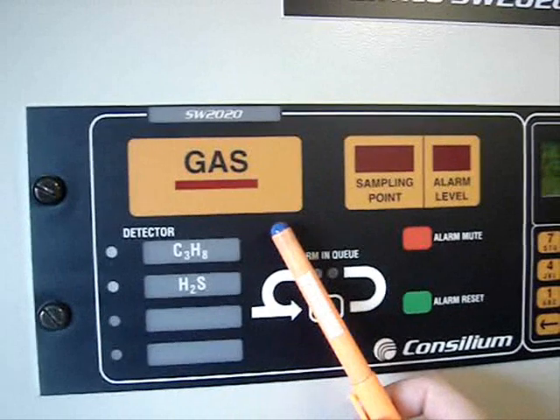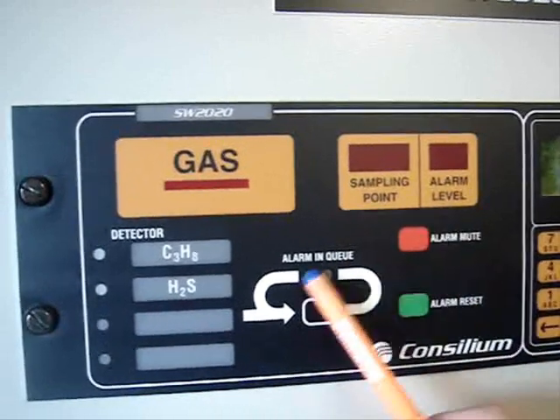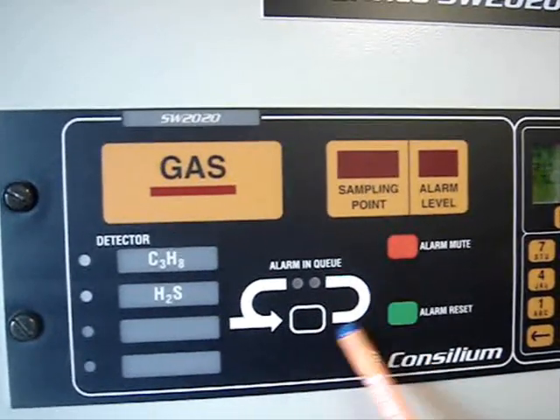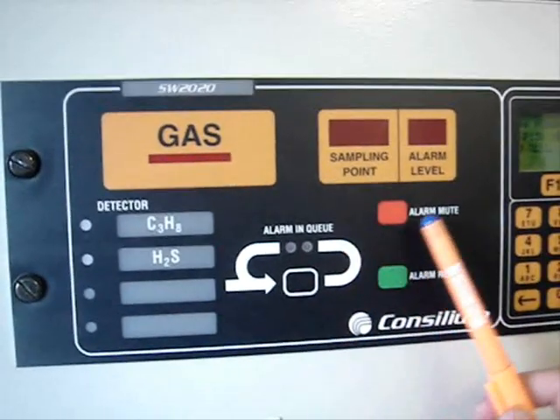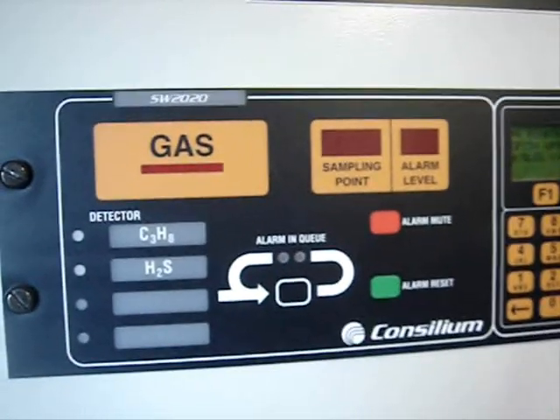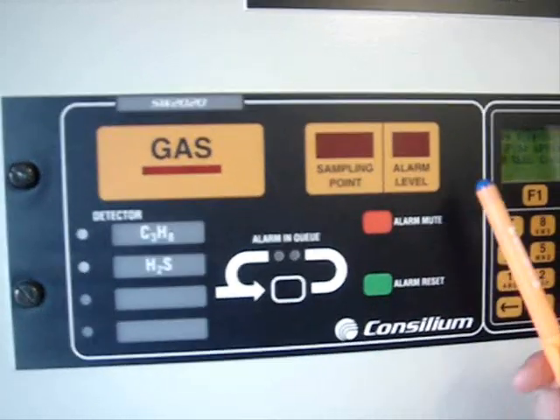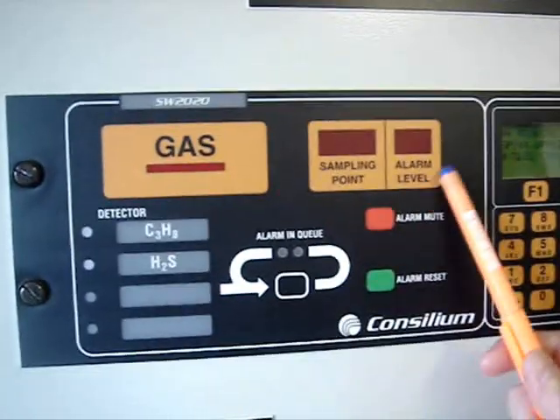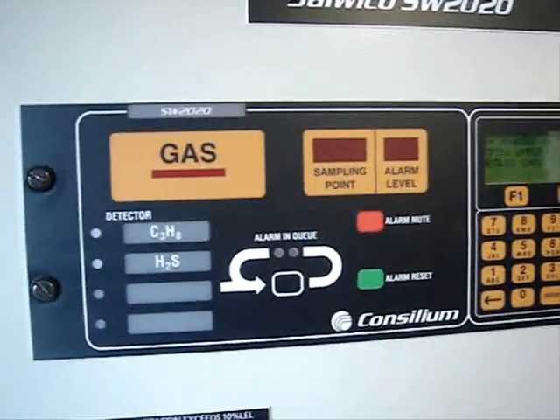The alarm unit of the system consists of two gas detectors — hydrocarbons and hydrogen sulfide — and three buttons. The alarm in queue button gives you the ability to change the sampling points with the alarm key. The alarm mute button will mute the alarm, and the alarm reset button will reset the alarm when the alarm disappears, when there is no gas detected on the sampling point. The display will show you the sampling point number and the alarm level of the detected gas.